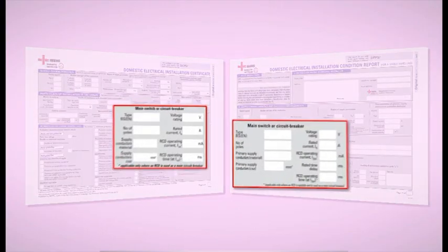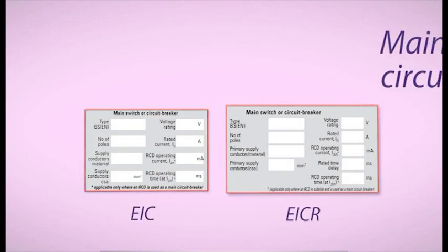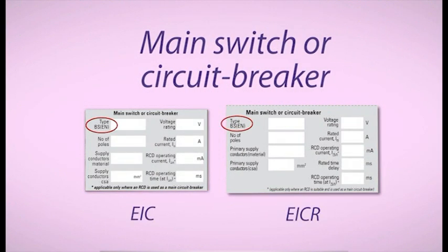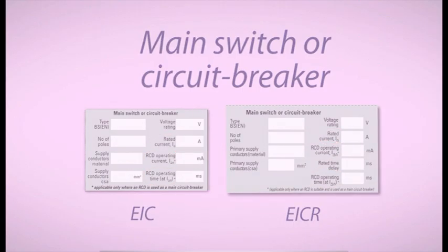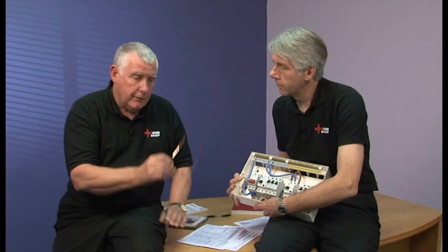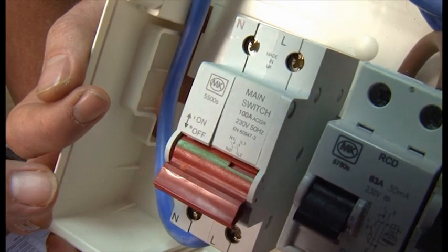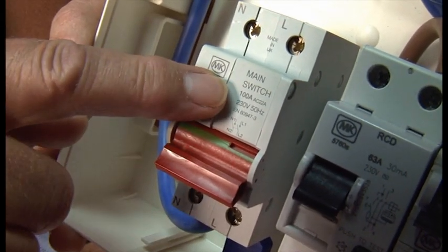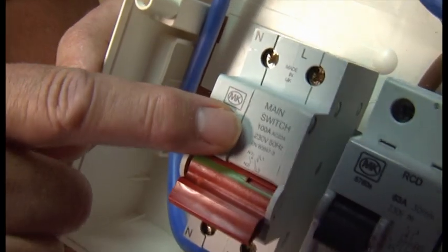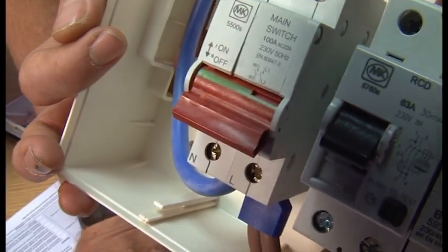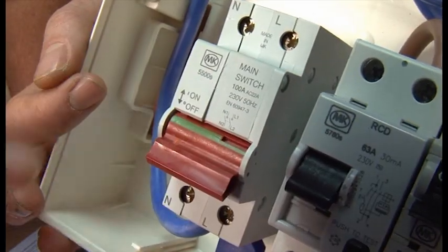Let's now look at the section for main switch or circuit breaker, which you won't find on the minor works certificate. Here we can see box type, voltage rating, number of poles, rated current IN, RCD operating current and its operating time, measured at fault current. A lot of this information can actually be picked up from the device. On this main switch here, we can see that the current rating is 100 amp, it's rated at 230 volts, it's a BS EN 60947-3 and it's a 2-pole device.